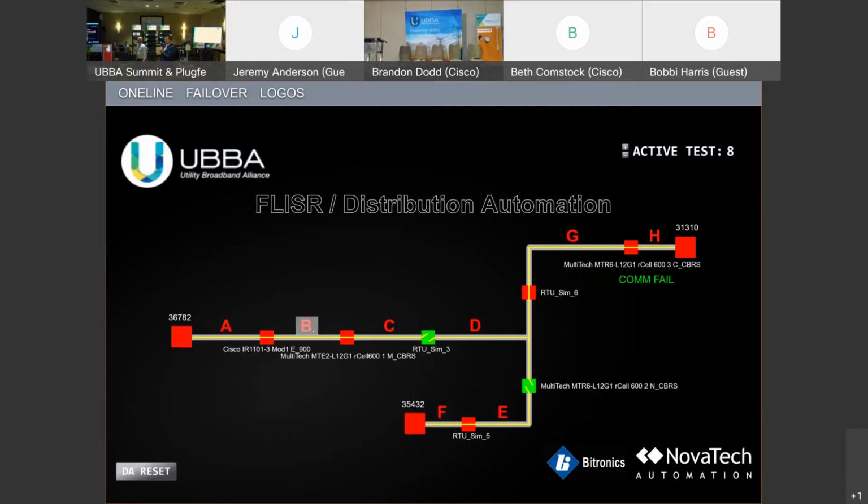One of the questions that we received yesterday, that I just assumed everybody knew the answer to, is: in most of the world, green is good and red is bad. That's still true in the electric industry, but it's relative to a different thing. The red and the green is relative to safety, or touch safety, being able to come in contact with the infrastructure. Red means that it is energized and that it would be bad for you to touch it. But it is good if we're in the business of having power flow. So a good source. Green is normally open, meaning there's not power flowing through there. There is energy on each side of that switch. It just has to close to pass by it.